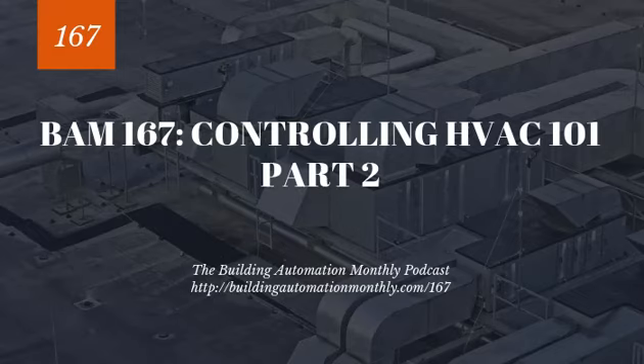And then we have temperature safeties. These are primarily low temp alarms, although sometimes you will have high temp alarms, especially with steam systems. I guess another contact safety would be condensate overflow as well. If you get a plug in your condensate line, that would be a potential safety, so you don't start flooding things. You could also have a float switch if you had DX and you're having a lot of condensate runoff. That could stop the unit as well. So there's a couple more contact safeties.